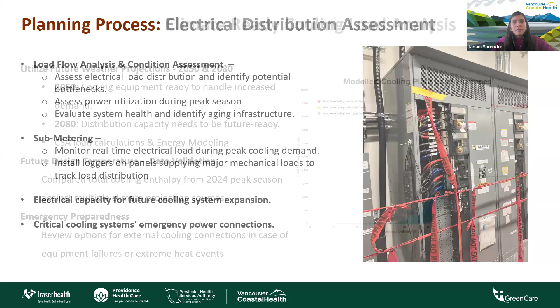As everybody knows, as cooling demand increases, the electrical load required to power the chiller, the AHU, and the cooling tower also increases. And without a strong electrical distribution system, we risk overloading our electrical circuits and causing system failures. So a key part of assessing the electrical distribution was tracking the load flow, because it helps us understand how much power is utilized, especially during the peak season. So the image here is of the data logger we installed in the electrical panel, so we can track real-time power usage during peak cooling demand, and that can help pinpoint the stress areas.